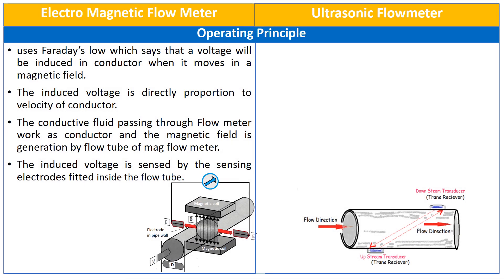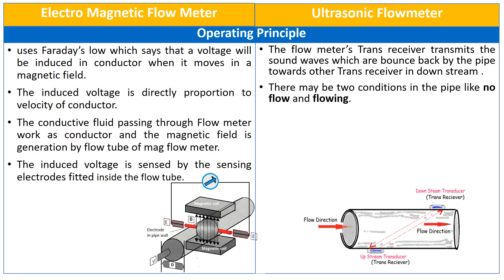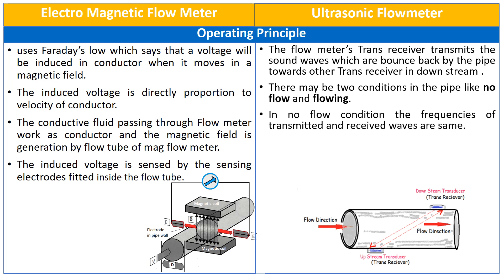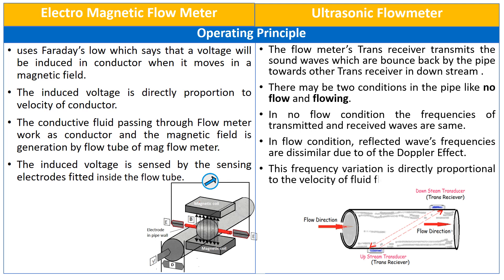In ultrasonic flow meters, the flow meter's transreceiver transmits sound waves which are bounced back by the pipe towards the other transreceiver in the downstream. There may be two conditions in the pipe: no flow and flow condition. In no flow condition, the frequencies of transmitted and received waves are the same. In flow condition, the reflected wave's frequencies are dissimilar due to the Doppler effect. This frequency variation is directly proportional to the velocity of fluid flowing into the pipe.